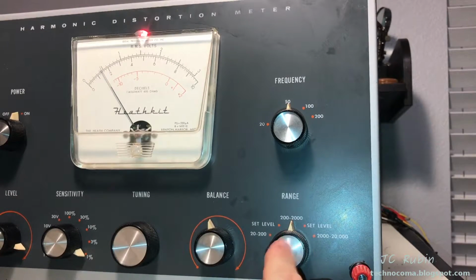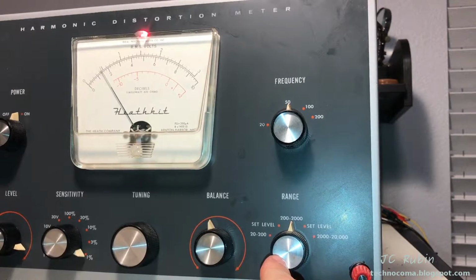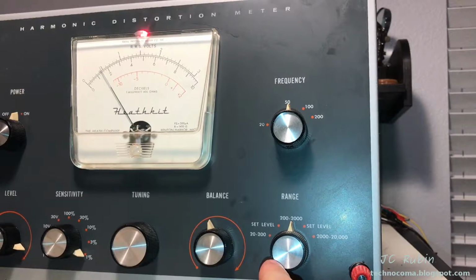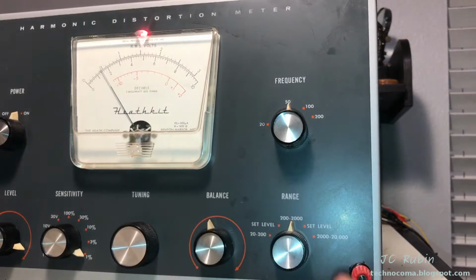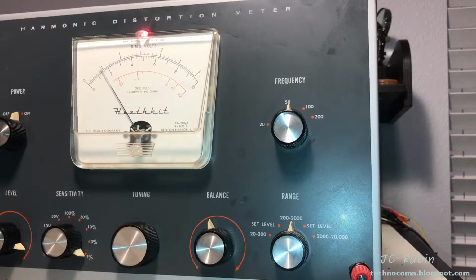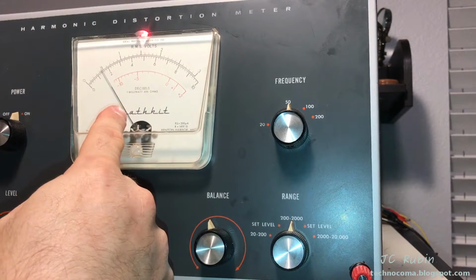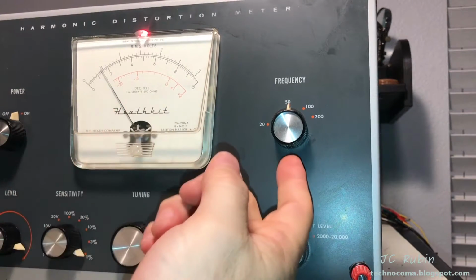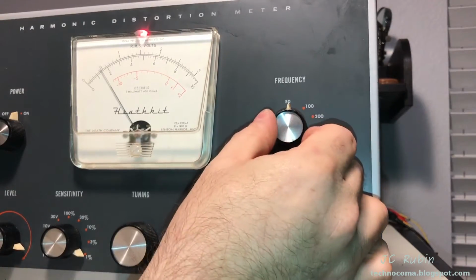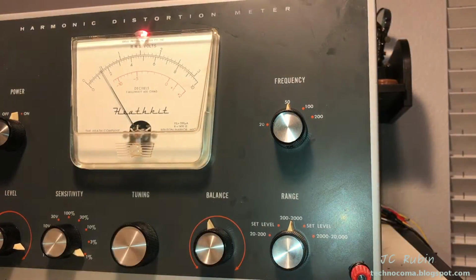Next step is fixing this, and I realize it's going to change because the ranges are not right. This has already been shown to be a fault, but we're going to do it anyway just for going through this in practice and whatnot. So basically what happens is I'm going to pick a known frequency on the function generator that I'll be able to align to this, and then I'm going to bring a maximum dip here, and I'll know I'll be on that frequency. I will loosen this knob, manually turn it into that position, and relock it down.